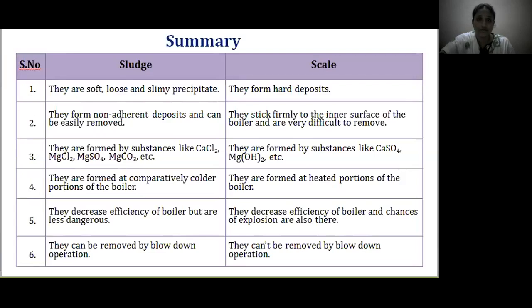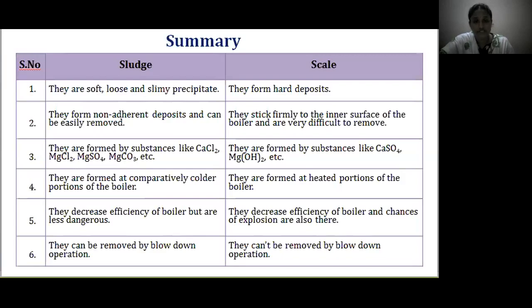Summary — comparison between sludges and scales: Scales are hard substances that stick firmly to the inner surface of the boiler and are very difficult to remove. Sludges are soft, loose and slimy precipitates that form non-adherent deposits and can be easily removed. Sludge-forming substances include calcium chloride, magnesium chloride, magnesium sulphate, and magnesium carbonate, and they form at comparatively colder portions of the boiler. Scale-forming substances include calcium sulphate, magnesium hydroxide, and calcium silicates, and they form at heated portions. Sludges decrease boiler efficiency but are less dangerous, whereas scales decrease efficiency and also carry a risk of explosion. Scales cannot be removed by blow-down operation, whereas sludges can be removed by blow-down operation.